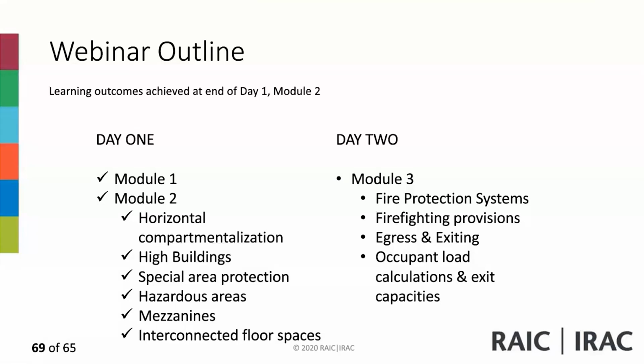But let's say, I'm sorry, maybe I'm digressing here with this question, I have a mezzanine that is enclosed with fire ratings of 45, completely enclosed. But above that, there is another level, and they're interconnected with stairs in between, and it's an A2 occupancy. Yeah, the second one would be considered a story, which would require a fire separation, as well as you will need to consider protecting it. You're not on the first level, you're on the second level. A fire separation would be required in your case.